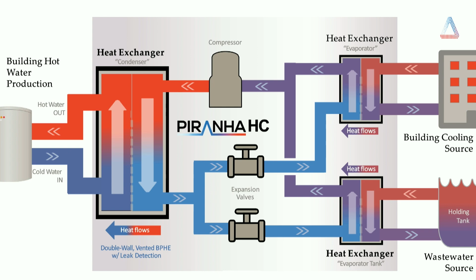If you're in an urban environment like we are in New York City, the job is going to design out and say, okay, I need 300 boreholes 500 feet deep. Well, the space doesn't allow you to drill 300 boreholes, but it'll allow you to drill 150. So you can intentionally short loop that ground heat exchanger, and we can take up the slack and control the temperature of that ground heat exchanger and control that creep, so that the ground heat exchanger can still deliver 55 to 80 degree entering fluid temperature to the hydronic systems in the building, okay?